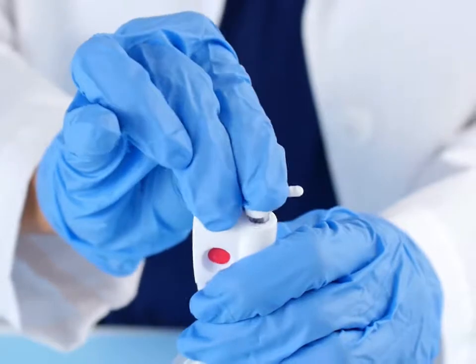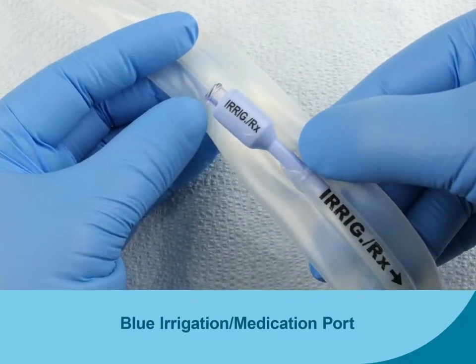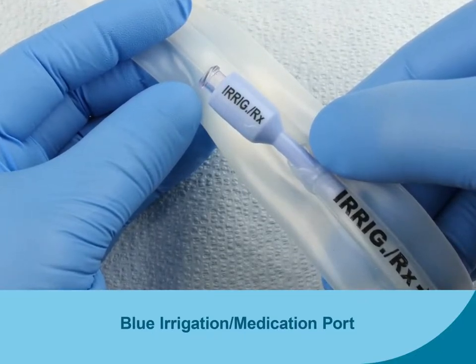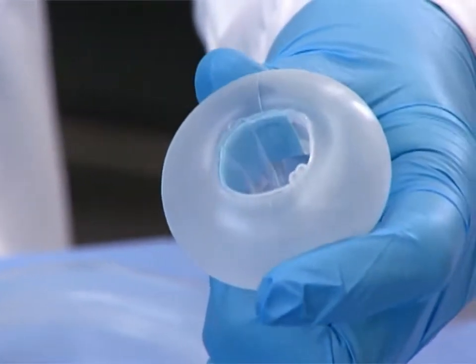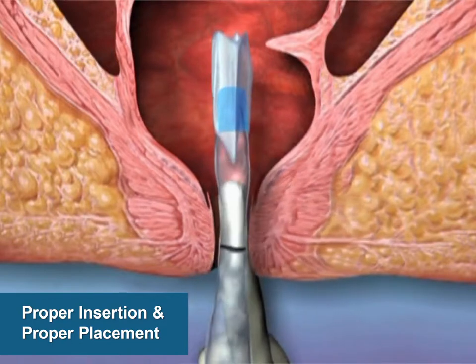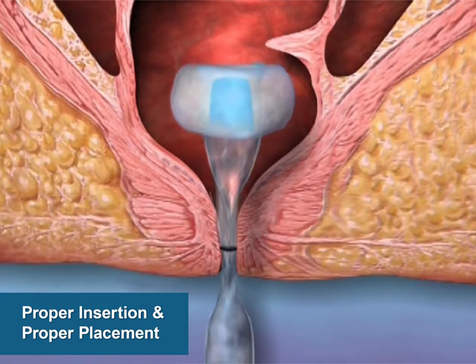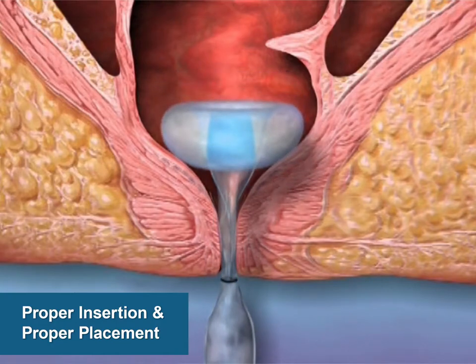The red fill indicator dome provides a visual and tactile indication when balloon overinflation occurs. A white cap is used to close off the white inflation port after balloon inflation. The blue port, marked IRRIG-RX, is used to flush the device if needed and administer medication if prescribed. A dark blue sampling port is also present if stool samples are required. The soft, flexible, low-pressure balloon is designed to help reduce the risk of tissue necrosis. Once inserted and inflated to the optimal volume, the retention balloon conforms above the sphincter anatomy on the rectal shelf to create an effective seal to minimize leakage and to safely divert and contain stool. Once in place, the drainage tube collapses to an 8 mm diameter, helping to minimize the impact on sphincter tone.